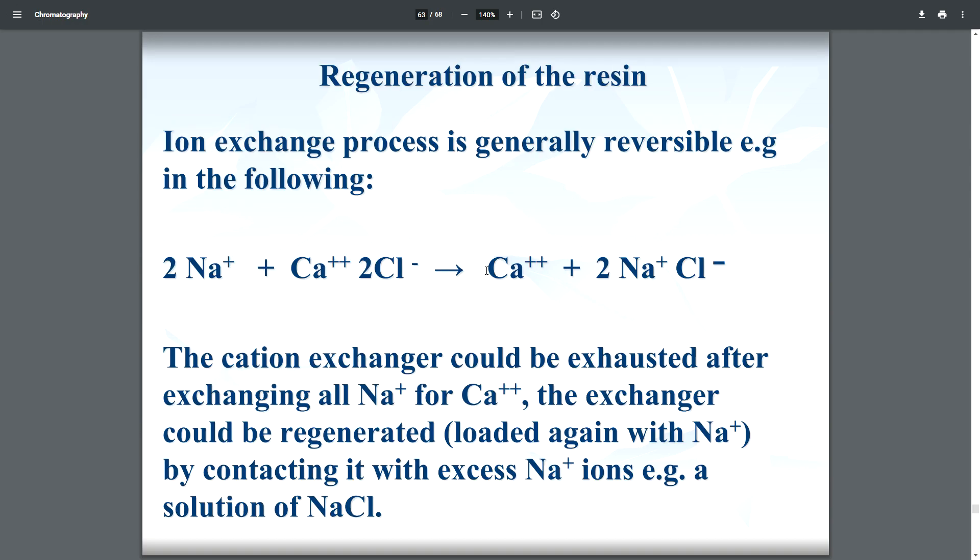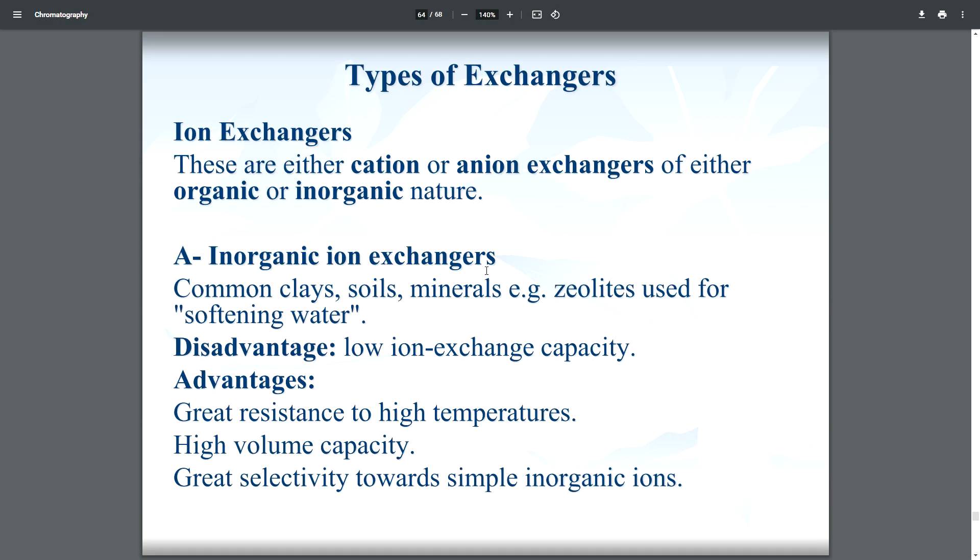The ion exchange process is generally reversible. For example: 2Na⁺ + Ca²⁺ + 2Cl⁻ ⇌ Ca²⁺ + 2Na⁺Cl⁻. After a cation exchanger is exhausted from exchanging all Na⁺ for Ca²⁺, it can be regenerated by contacting it with excess Na⁺ ions — for example, a solution of sodium chloride.